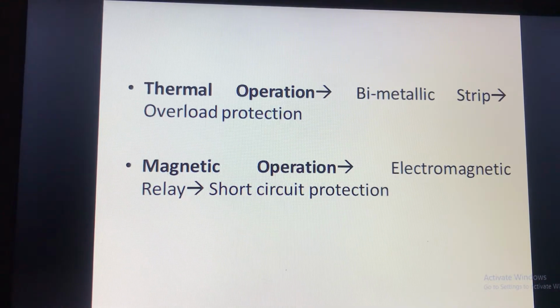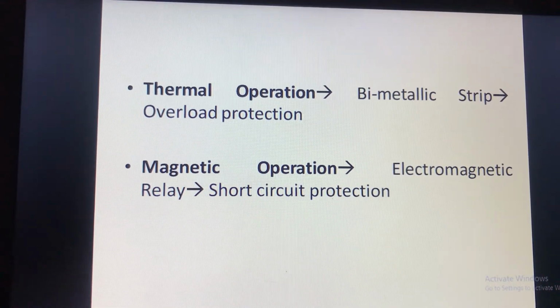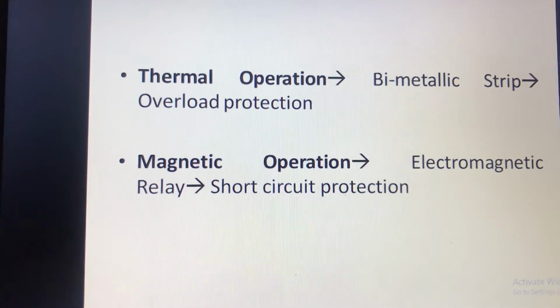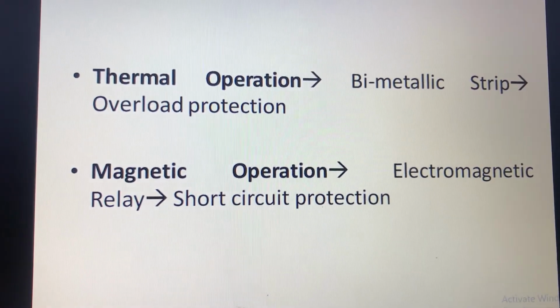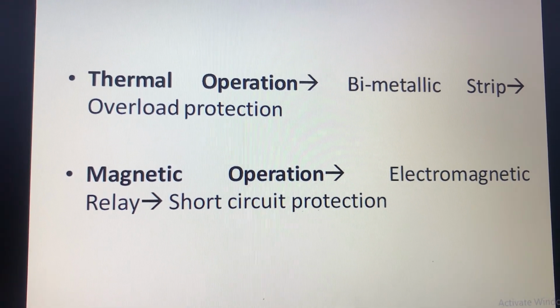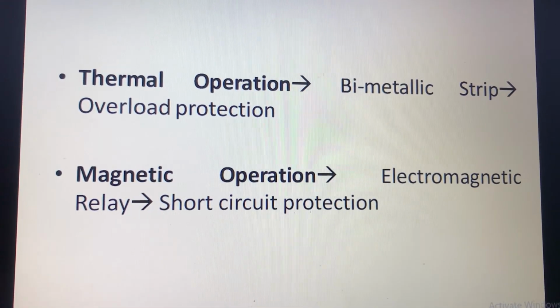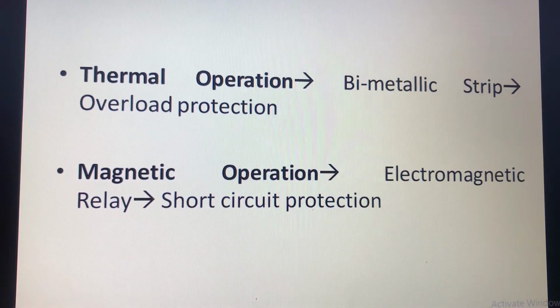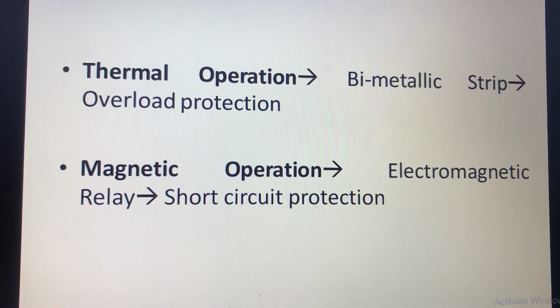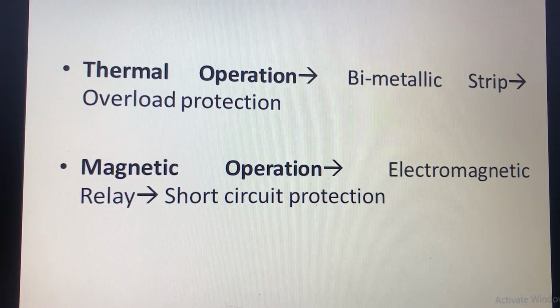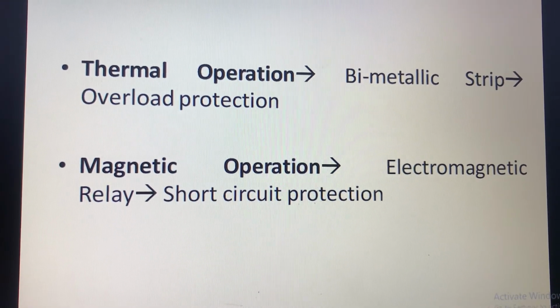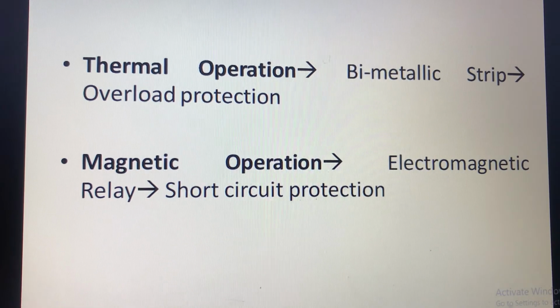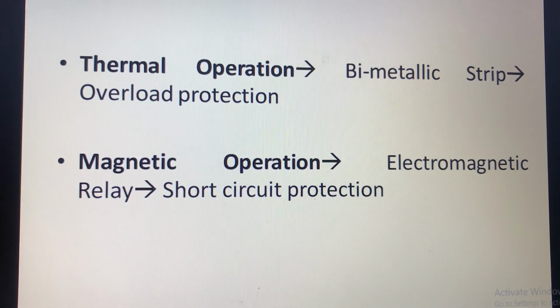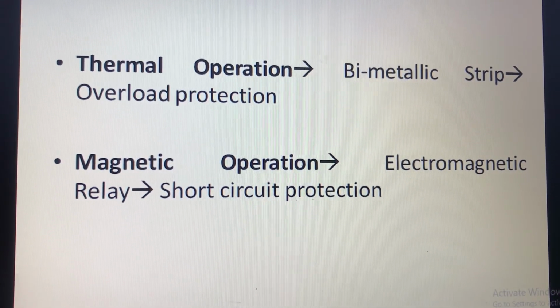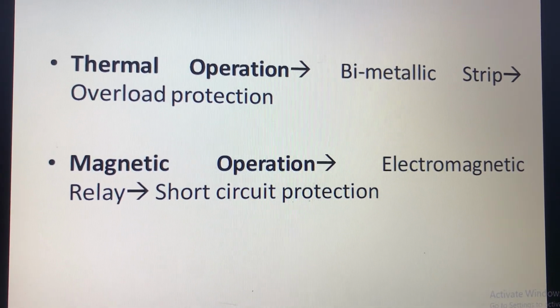So there are two types of operations. One is thermal operation and second one is magnetic operation. Thermal operation is provided by bimetallic strip, as we have seen in the diagram. In bimetallic strip, it is a combination of two metals having different temperature coefficient. Means there are two metals which are combined together, so they have different temperature coefficient. One metal, in simple language, you can say one metal bends earlier as compared to the other one.